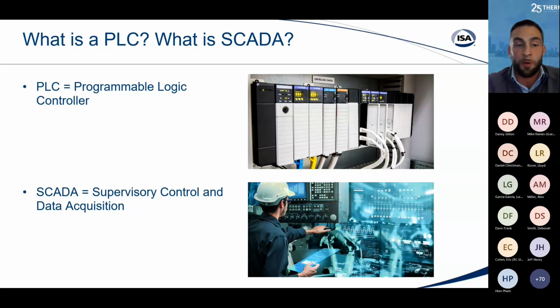Some typical components that make up the SCADA system would be the application software, the databases, and the computer hardware such as servers and workstations. I also want to mention the network infrastructure that ties the PLC, SCADA, and equipment together. This is made up of switches and physical infrastructure such as cables and network configuration. It's important to note that the PLC platform, the SCADA platform, and some of the components that make up those systems can be from the same or different manufacturers, and they're typically integrated using a systems integrator such as Thermo Systems.